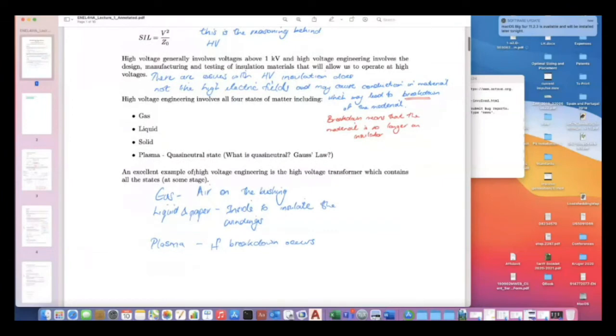An excellent example of high voltage engineering that contains all these states at some stage is the transformer. We looked at that in that video. So it'll have gas insulation. There'll be the air on the outside of the bushing. Inside the transformer, as you know from Design 3, you've got transformer oil and paper. So there's your solid and liquid insulation. And if breakdown occurs, you've got plasma.